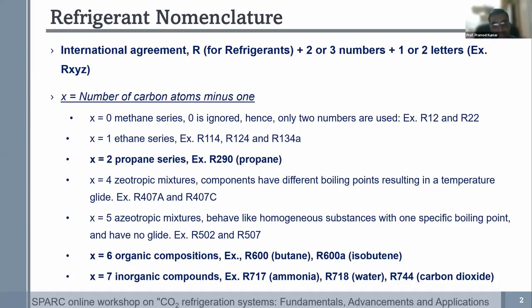Just in academic interest, how does the number 744 get designated to carbon dioxide? If you look at the refrigerant nomenclature, this is an international agreement. R stands for refrigerant. Then it is followed by 2 or 3 numbers and then 1 or 2 letters. Briefly going into propane, which is a natural refrigerant, 2 stands for the propane series. So R290 is essentially propane.